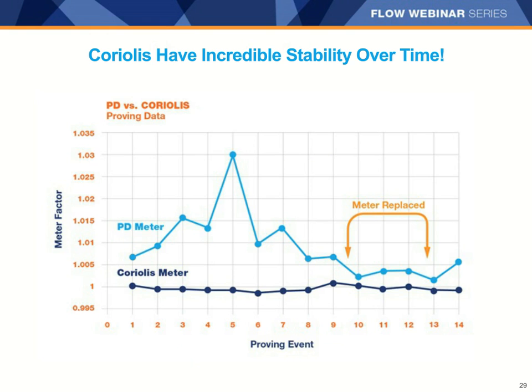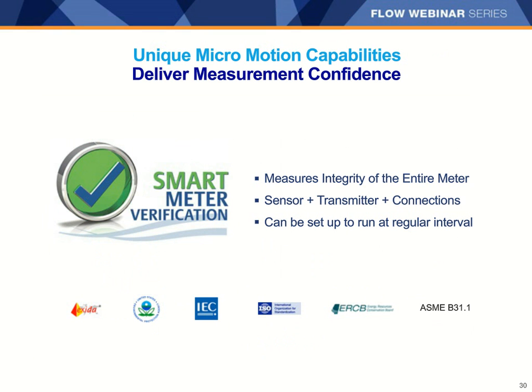Micromotion meters have very good long-term stability and can reduce or eliminate unnecessary calibrations in many applications. When a measurement is important, like for fiscal custody transfer, safety, or critical process control, you want the confidence to know that your flow measurement is reading right. Emerson is focused on delivering that with our micromotion Coriolis meters through smart meter verification. We will be discussing smart meter verification next.